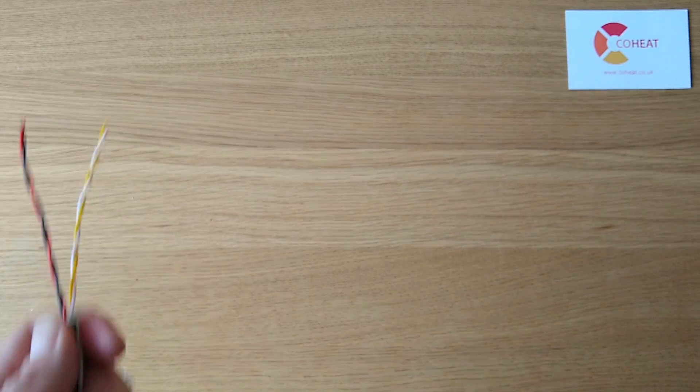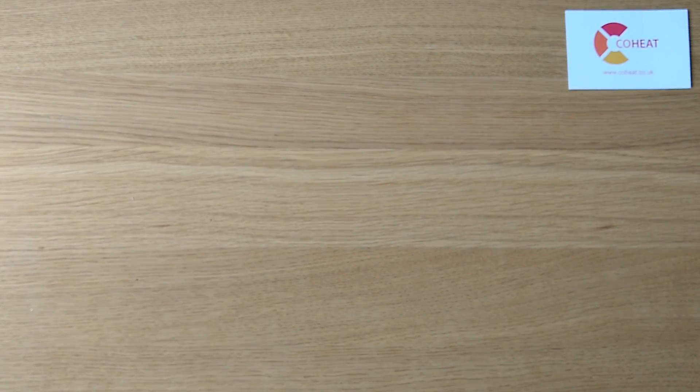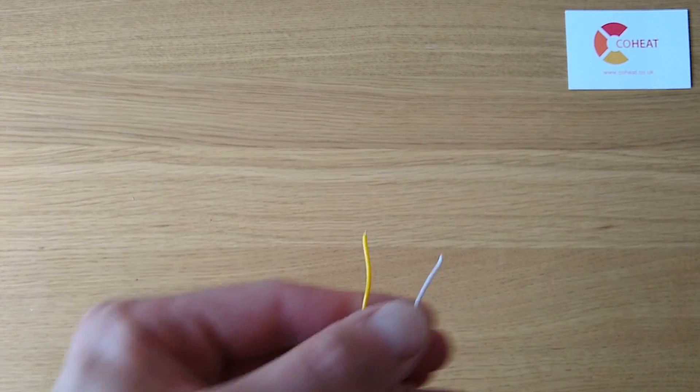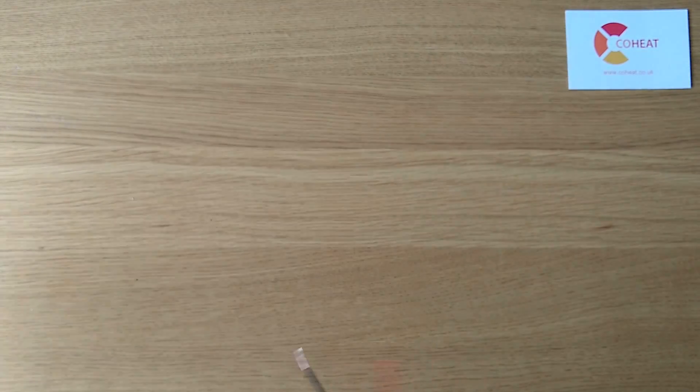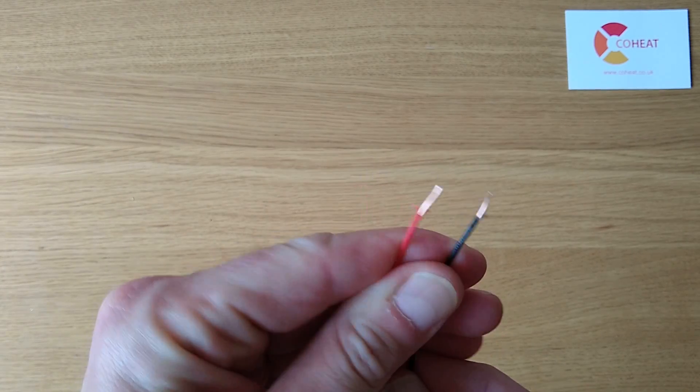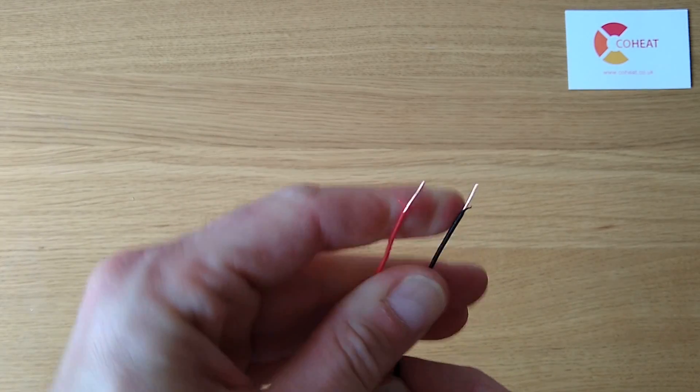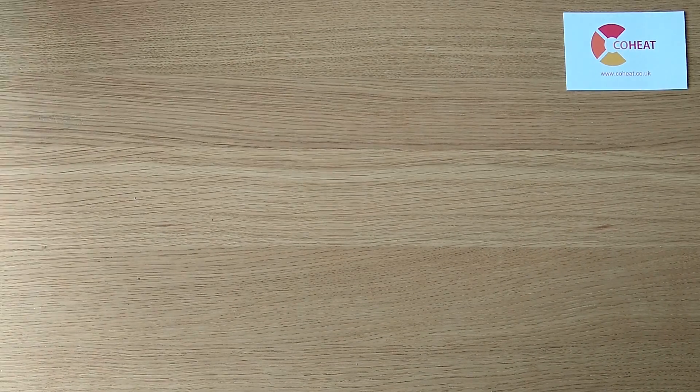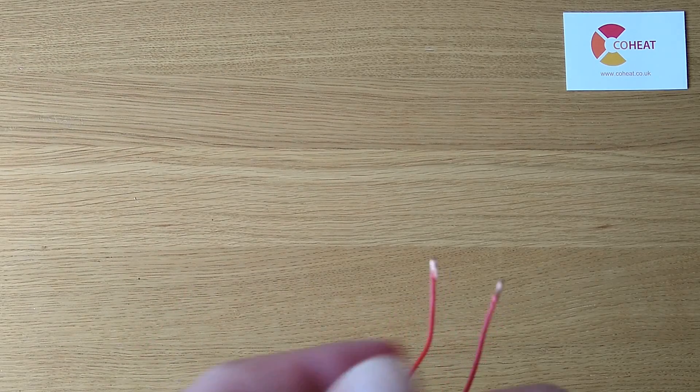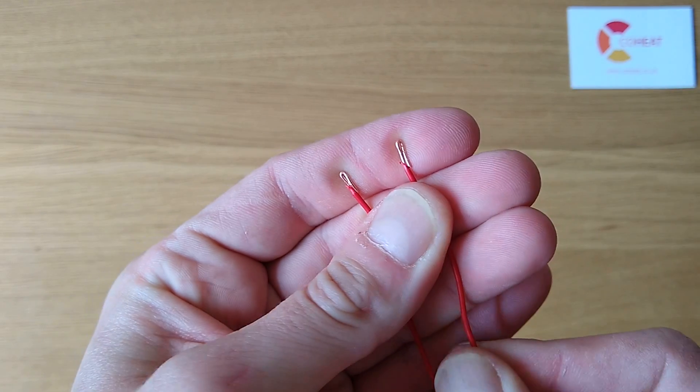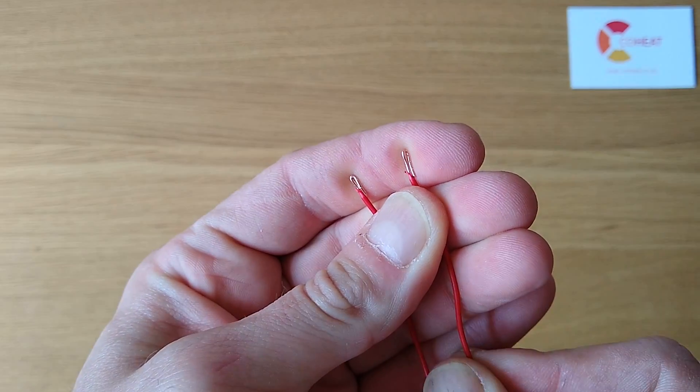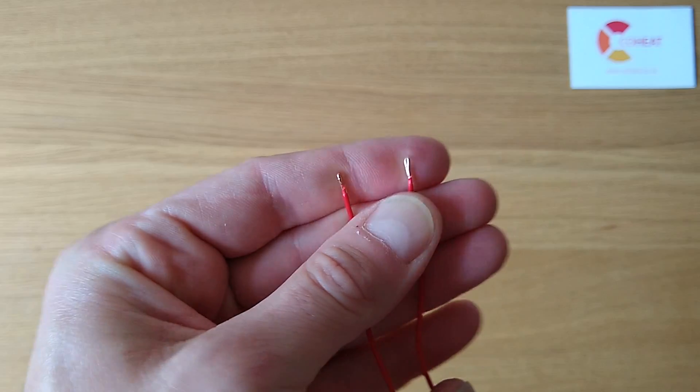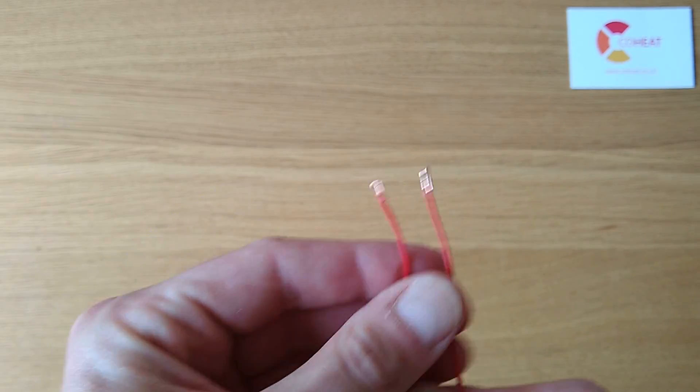These are solid core. With the right type of connector, they can be joined without stripping them. By stripping them and leaving them single, these are thick enough to take a terminal block. Or fold them over, as if it was a pair of twin and earth cable into a consumer unit or a faceplate.